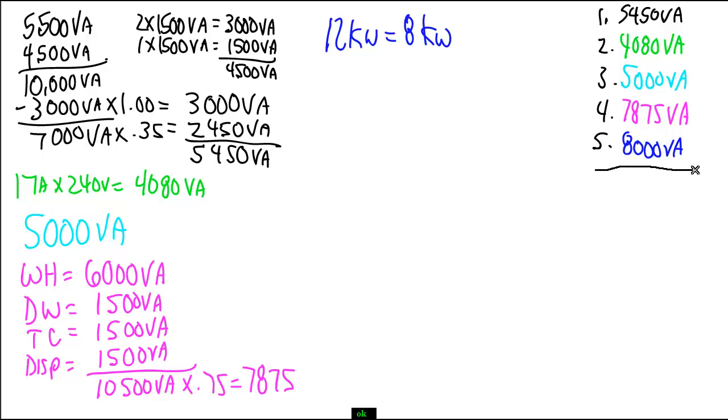Let's get ready to add this up. If I take all of these and I add them up, I get 30,405 VA. I'm going to divide that by 240 volts, because that's our nominal voltage. Because what we're looking here for is our feeder size for this service. So if I divide that out by 240 volts, I get approximately 127 amps. So I'm going to put a 150 amp service in this house.